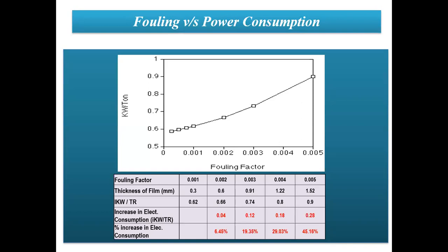So here is a wonderful depiction of how fouling versus power consumption increases based on only scaling, if proper treatment is not there. Here you can see the fouling factor at the start of the project was 0.001. That is basically a 0.3 mm thickness of film, film in the sense of the deposition of scale or biofilm, whatever. At that time, the IKW of the fresh chiller per ton was about 0.62. Within 3 or 4 months, it reached a fouling factor of 0.002. So what happened? You can see there is a sharp increase in the electricity consumption of 6.45%.